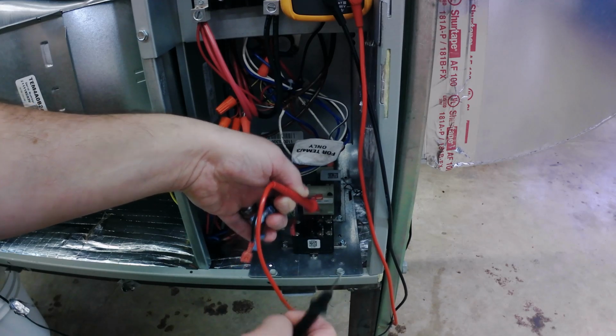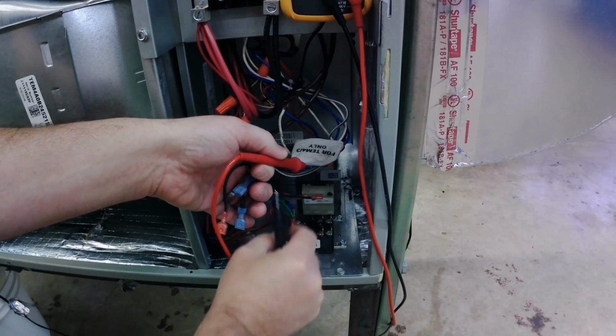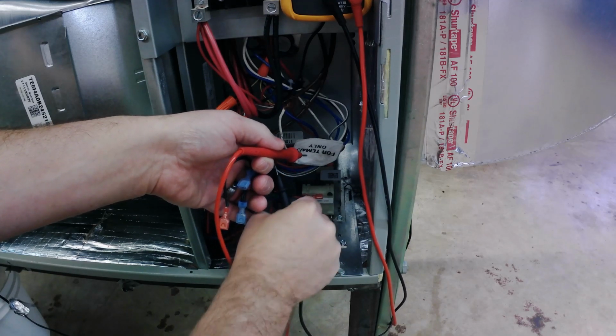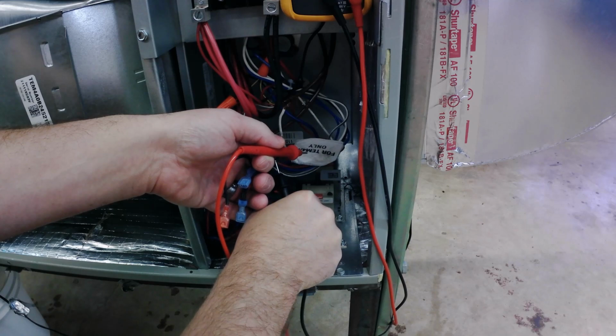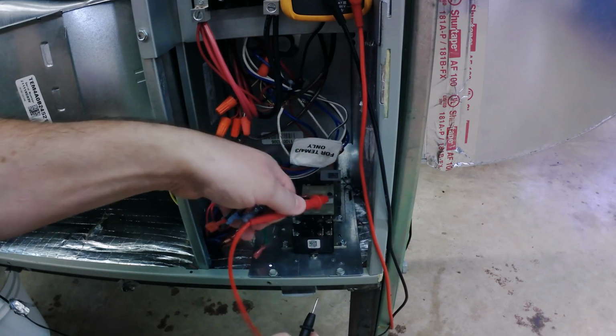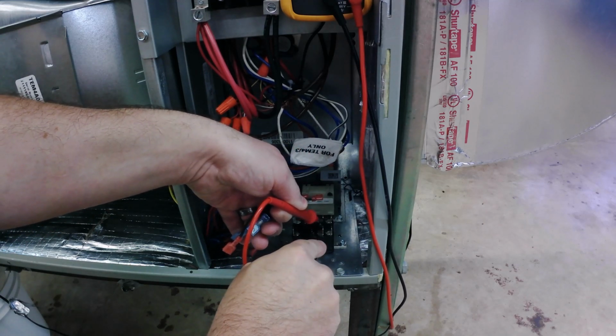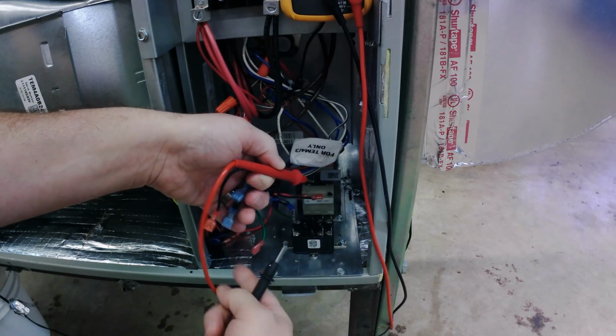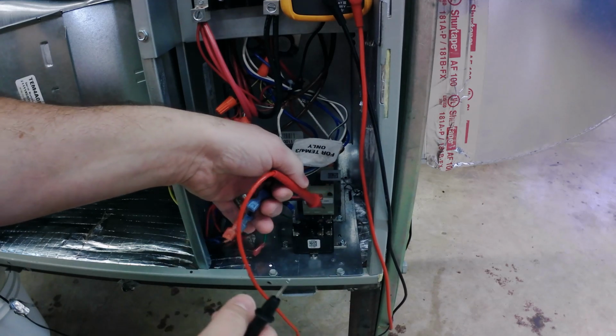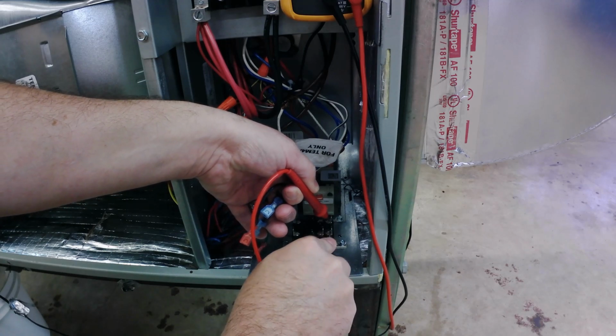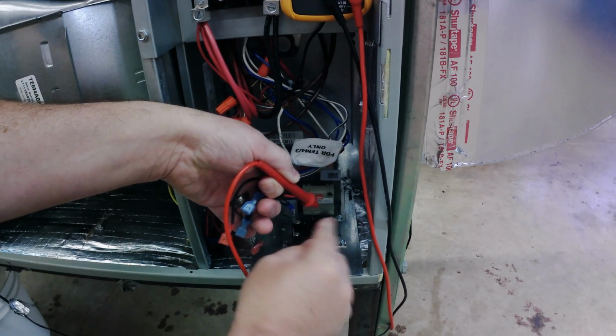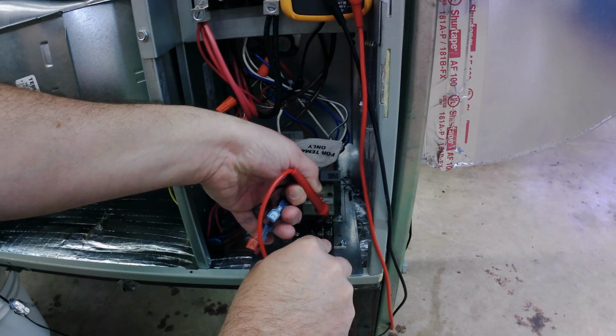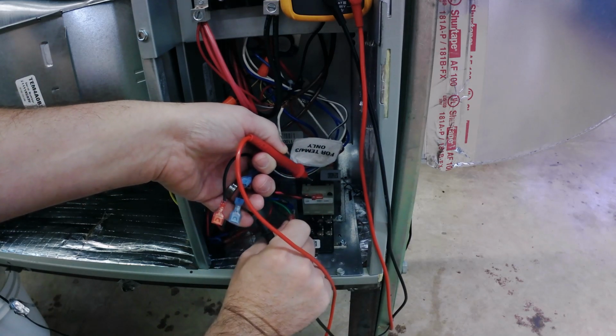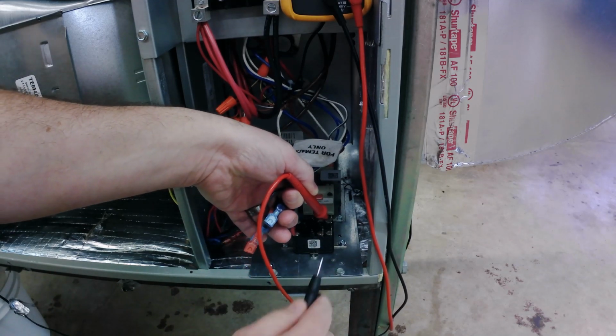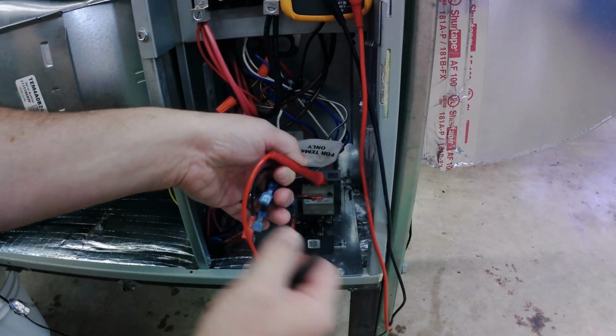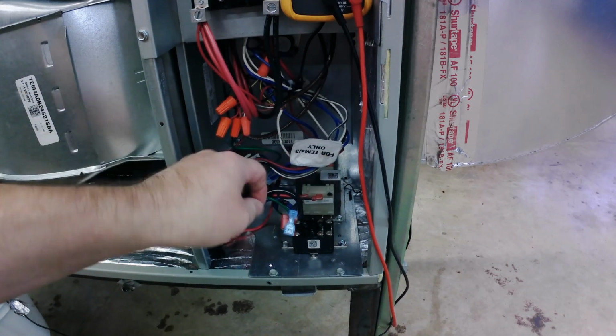Now that's only half the check. The real check would be if you remove power on the low voltage, did it go back closed? And it did, so that's good. Now, since I've got power off the coil, I'm going to ohm out the open side, and it's open, no beep. I got a beep when I touch my leads. I got no beep when I do the switch. If I were to reapply coil voltage, that switch should close. And it did.